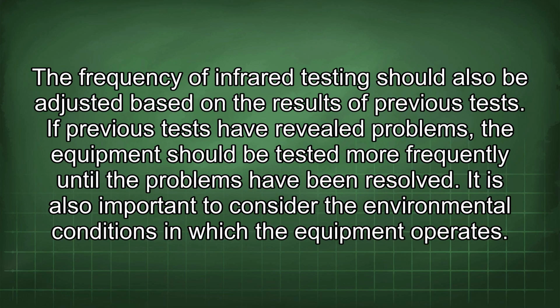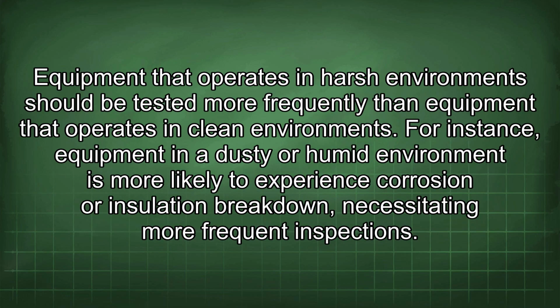The frequency of infrared testing should also be adjusted based on the results of previous tests. If previous tests have revealed problems, the equipment should be tested more frequently until the problems have been resolved. It is also important to consider the environmental conditions in which the equipment operates. Equipment that operates in harsh environments should be tested more frequently than equipment that operates in clean environments. For instance, equipment in a dusty or humid environment is more likely to experience corrosion or insulation breakdown, necessitating more frequent inspections.